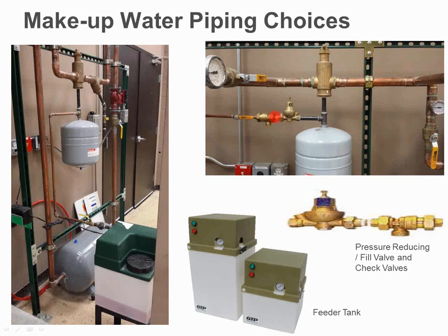The next valve next to it is a pressure reducing valve. All our city main pressures normally come in anywhere from 30 to 60 psi. Well, if I put that 30 or 60 psi directly into my boiler, which has a 30-pound relief valve, what's happening? It's going to come right out the relief valve. So what a pressure reducing valve does, just like it says, it reduces the pressure. Normally these valves are set for about 12 psi.